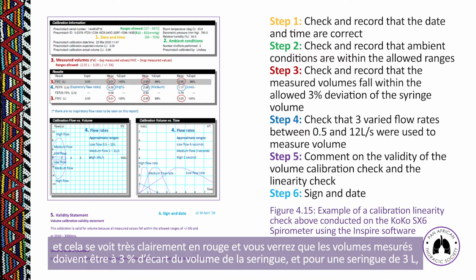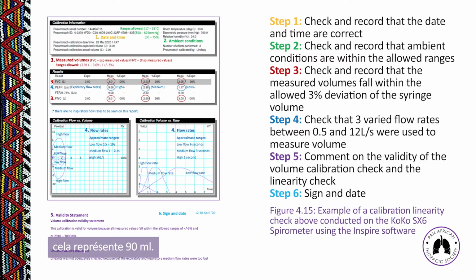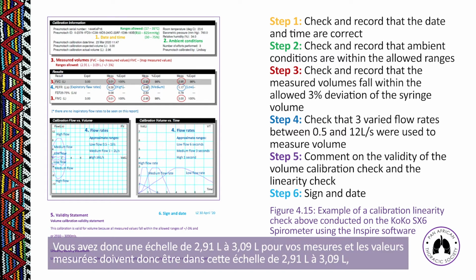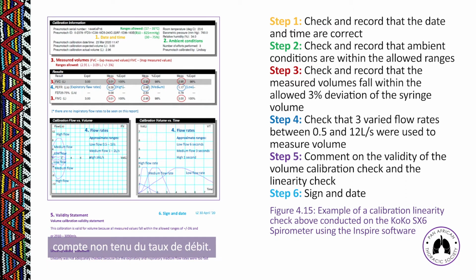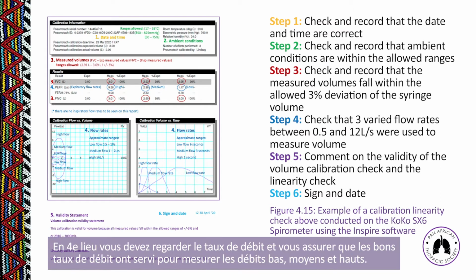when using a 3-liter syringe, that's 90 mils of 3 liters. So you're allowed a range of 2.91 liters to 3.09 liters. For those values to be measured, the measured values must be within 2.91 to 3.09 liters at any flow rate. Fourthly, you would want to look at the flow rates and make sure that the correct flow rates have been used for low, medium, and high flow.